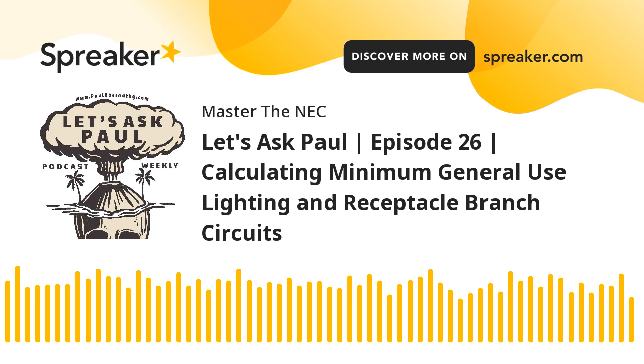Now, the first thing that we want to do here is say, okay, we need to take that, and we know what we're dealing with: general lighting and general use receptacles, right? And those are 120 volts. Now, we're using nominal voltage. Code tells us to do that. We're going to be using 120. So we need to find the overall amps that we're working with here. All right, so how do we do this? Well, it's 4,200 VA divided by 120. So it's a 120 volt nominal system. And again, we're just going for the general lighting, general use receptacles. And that equals 4,200 divided by 120 equals 35 amperes. Now we know the amps, and we know that we want these to be 15 amp branch circuits.